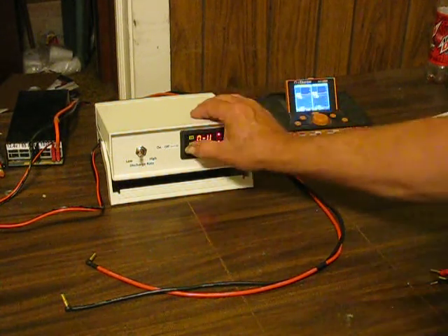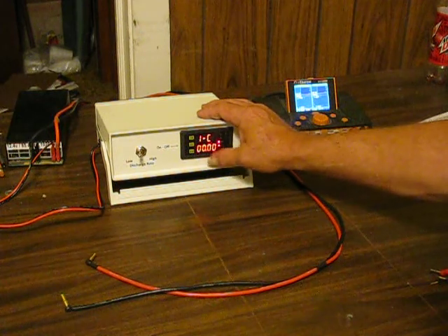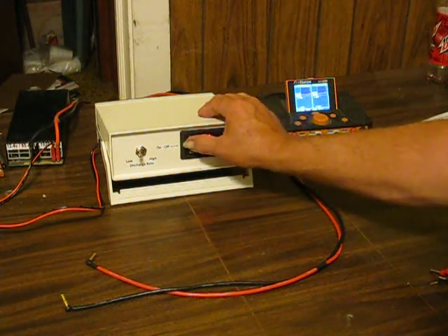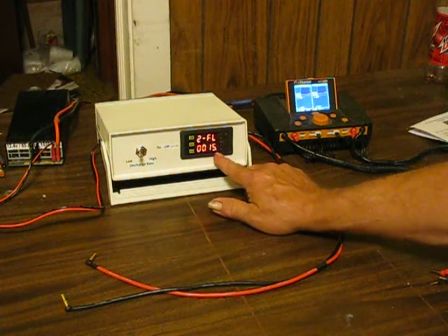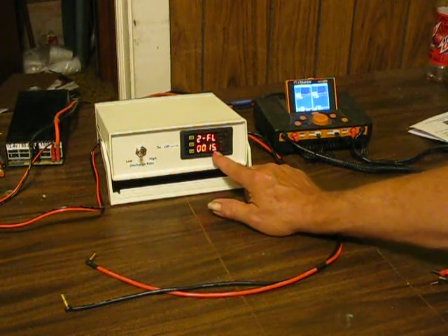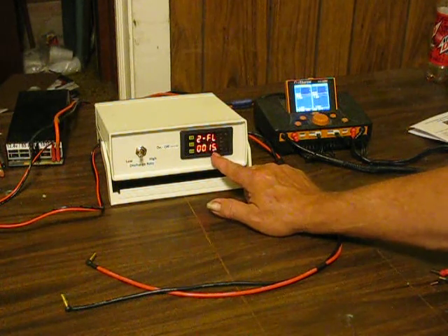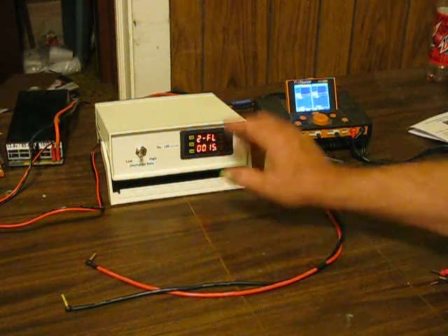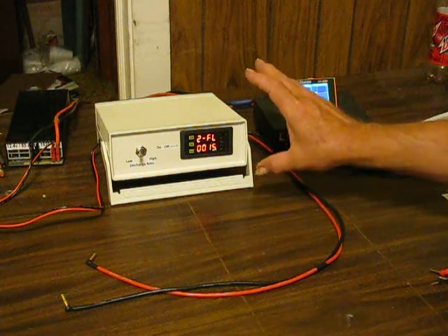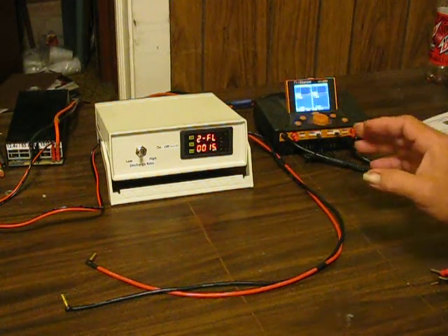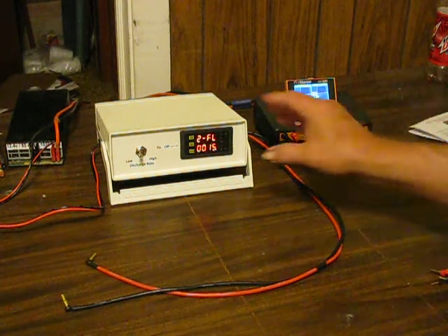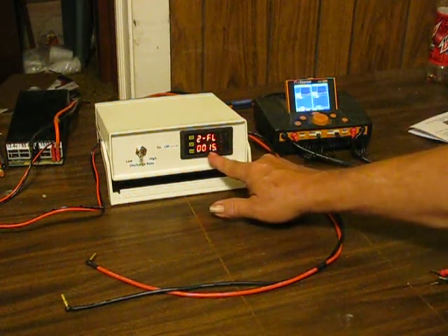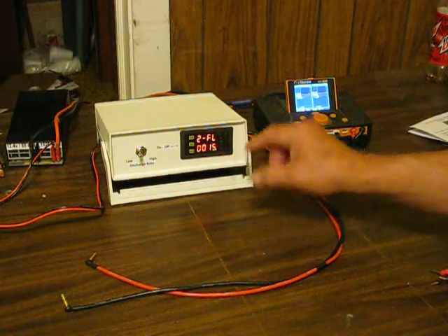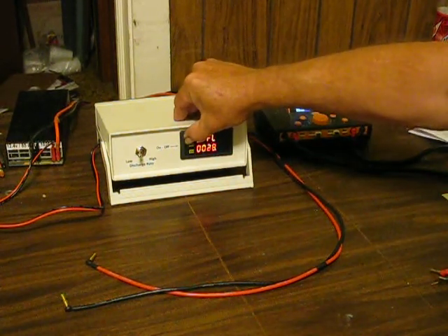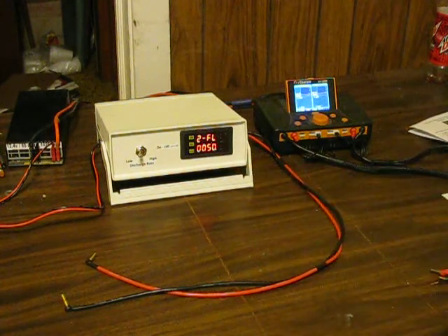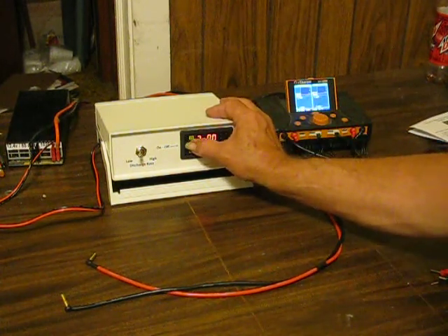There's a couple readings here we'll go on through. We'll get to that, that's the current setting. We'll go on by that. Number 2, that is the amperage setting. We've got a 50 amp shunt in this unit, which means it could handle up to 50 amps. We're only going to use about 20 to 25 max, but we want that set at 50. When it resets, a lot of times it'll go back to 15. We want that at 50. Hold that top button down until that reads 50, like that. We'll step on through here.